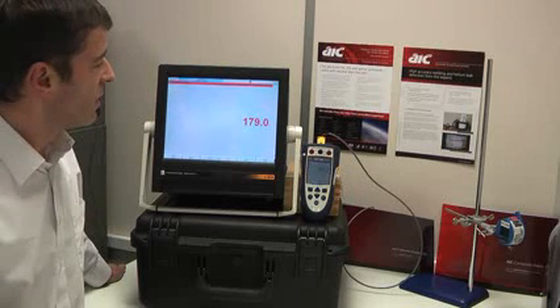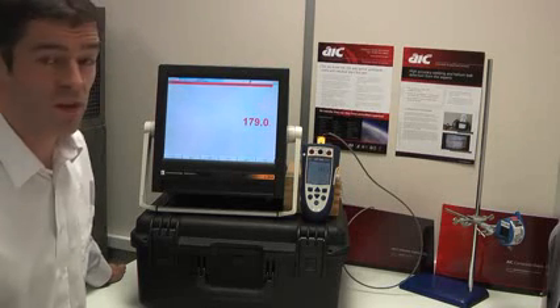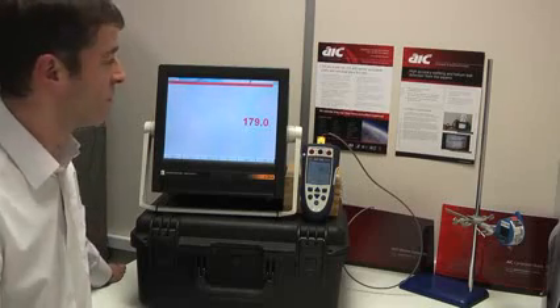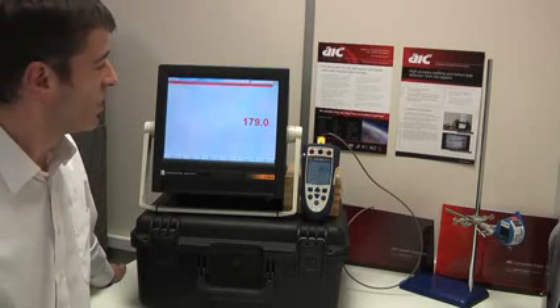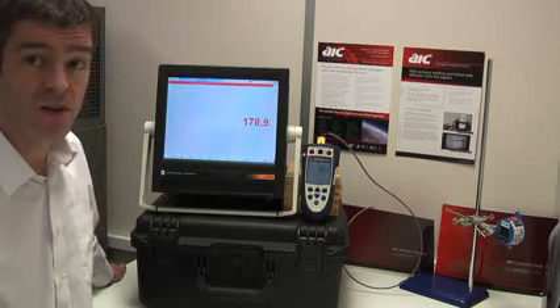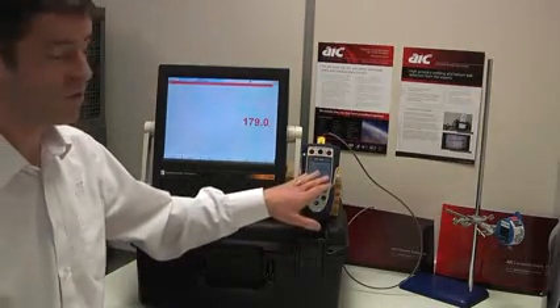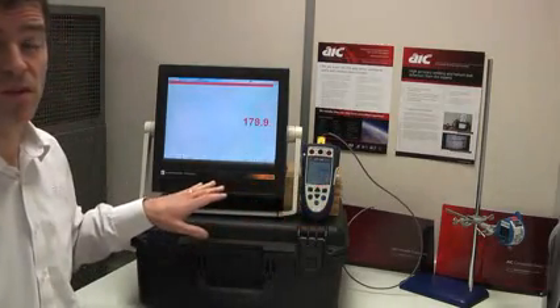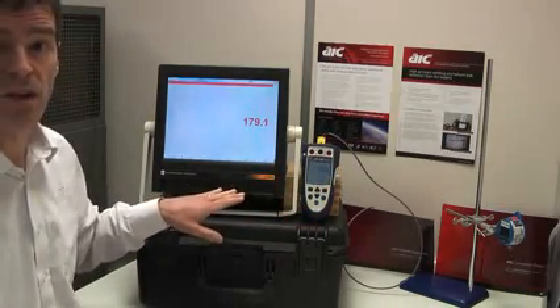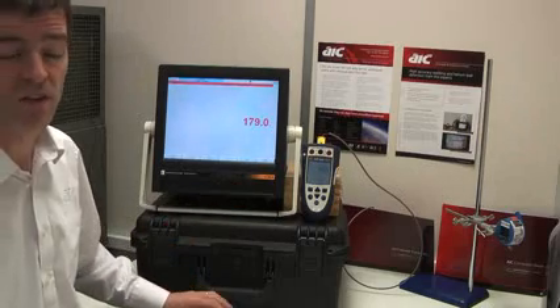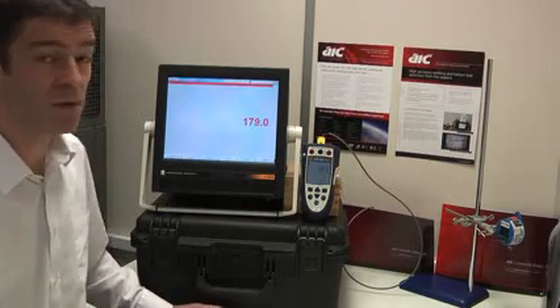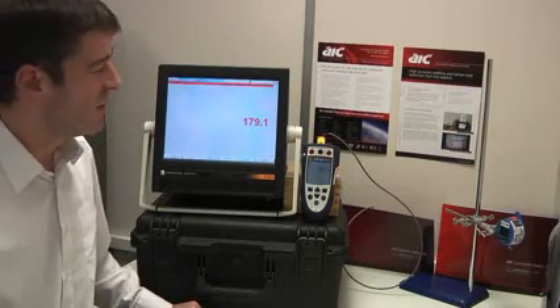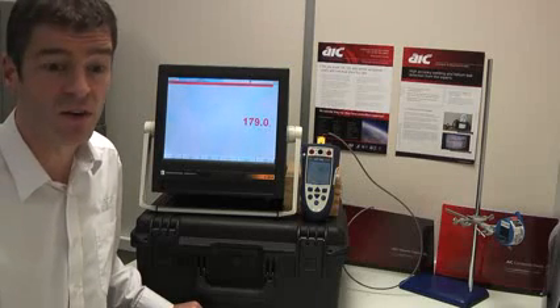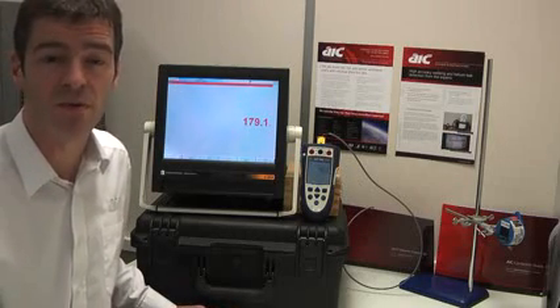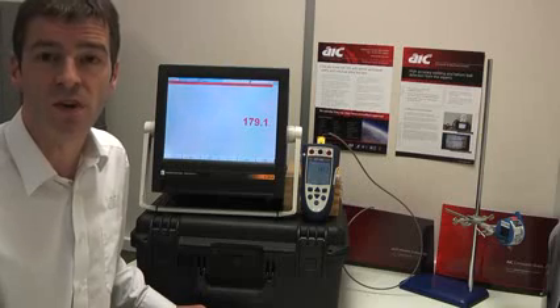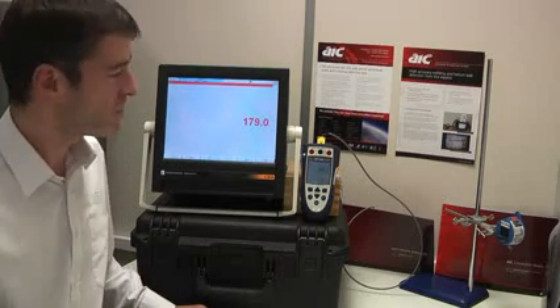So all of the signal, say for 1 degree perhaps, that's significant in this calibration is what comes out of the process calibrator and is measured at the junctions at the back of the instrument under test. And the cable in the middle of it, if it has even a very significant error, like it's completely the wrong kind of cable, this won't be shown up with this type of calibration.